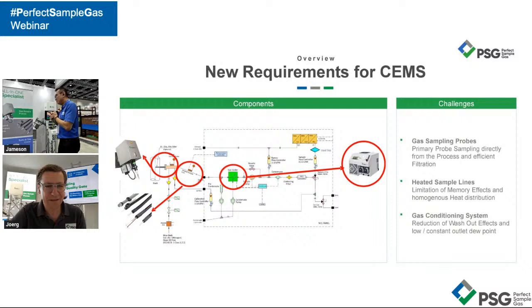Yeah, definitely, it's all about sampling, right? First and foremost, we all talk about representation. How representative is the gas from the pickup point all the way to the gas analyzer? During this journey, the sample probe itself is the only component in the extractive system that is exposed to the duct. Therefore, the first stage, we have to get it right.